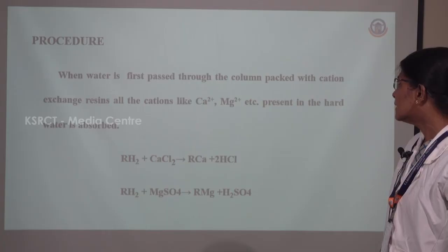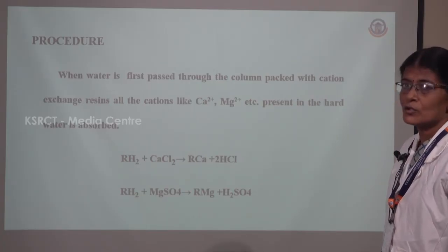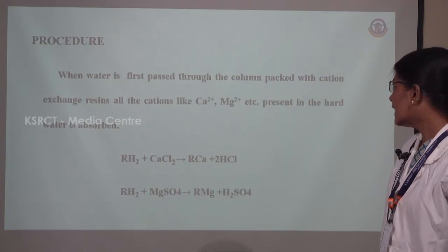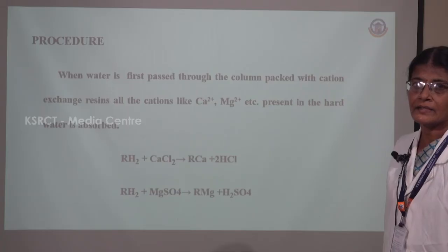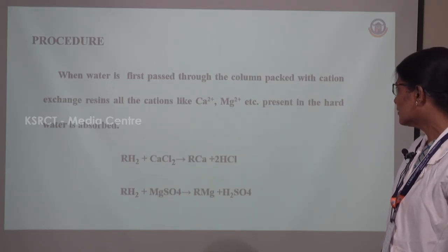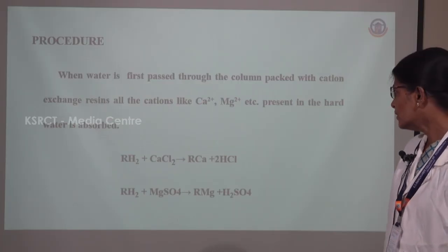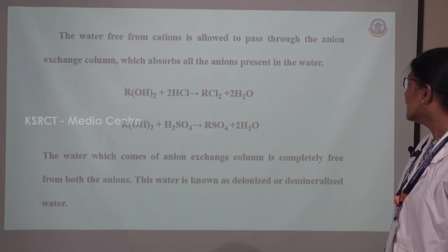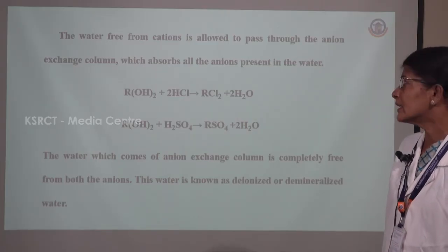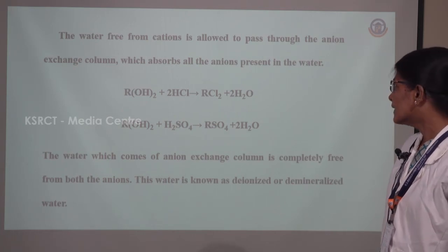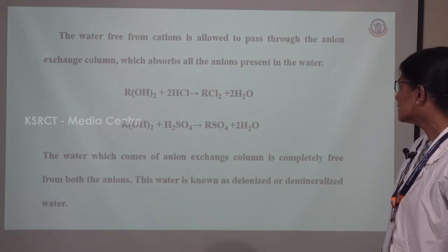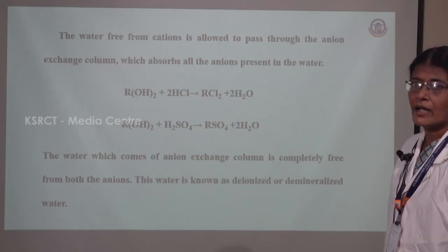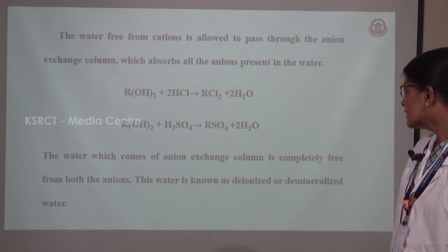The procedure involves two filters. Water is first allowed to pass through the first column packed with cation exchange resins, where calcium and magnesium ions are absorbed. The reactions in the first column are: RH₂ + CaCl₂ → RCa + 2HCl; RH₂ + MgSO₄ → RMg + H₂SO₄. The water coming out of the first column, which is free from cations, is then passed through the second column — the anion exchange column — which absorbs all the anions. The reactions are: ROH₂ + 2HCl → RCl₂ + 2H₂O; ROH₂ + H₂SO₄ → RSO₄ + 2H₂O.